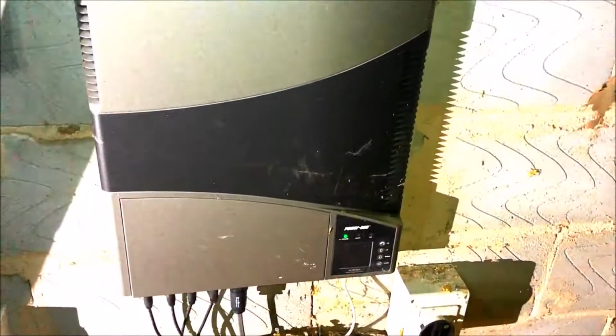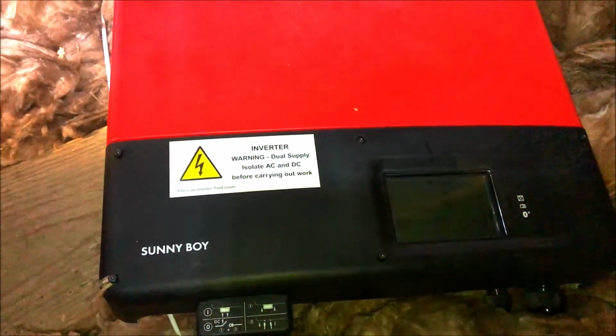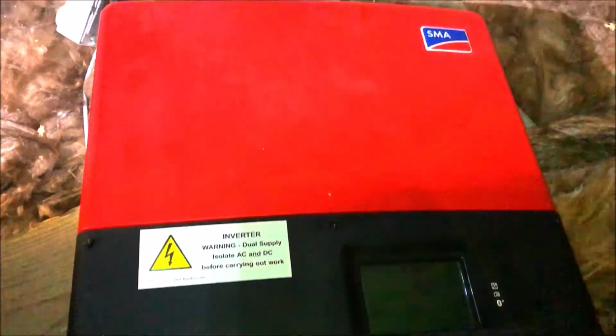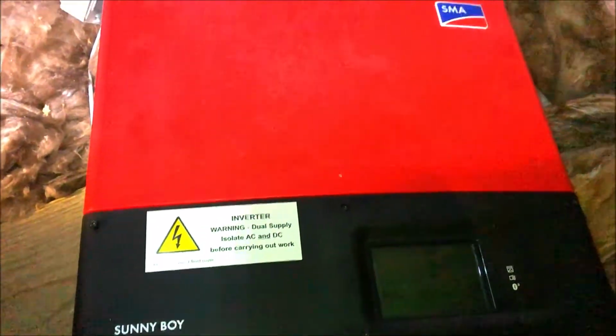So today's project, we shall replace the Power One inverter that we've had fitted for about 7 years now. When it played up the other day, we lost all power, we lost all solar, it just cut out. We left it off for 2 days, reset it, and eventually it came back on again, so it's working again now. But in the meantime, I went out and bought a Sunny Boy 4000 inverter, which is supposedly a better quality one. So what we're going to do now is take this one off and replace it.